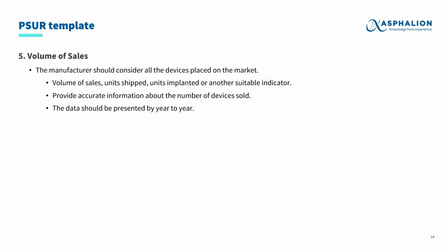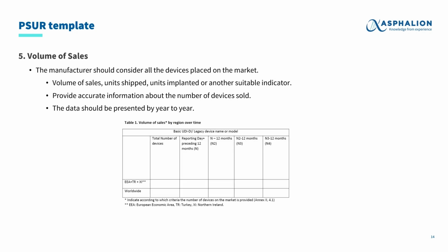Following this section, information regarding the number of sales during the reporting period should be described. The manufacturer should consider all devices placed on the market, providing volume of sales, units shipped, units implanted in case of implantable devices, and any other suitable indicator for representing the number of sales. Importantly, the manufacturer should provide accurate information regarding the number of sales, and if possible, the data should be presented year to year. This is an example of a table provided by the guideline that can be used by manufacturers to describe or detail the number of sales of a medical device per year and country.